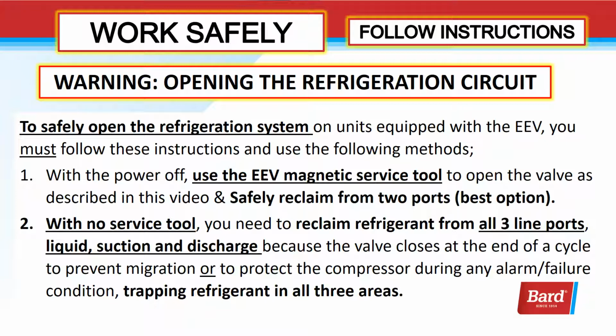With the power off, you can use the electronic expansion valve magnetic service tool to open the valve as described in this video and safely reclaim refrigerant from the two ports located near the compressor. With no service tool, you need to reclaim refrigerant from all three line ports, and that would be the liquid line, suction line, and discharge line. Because the valve closes at the end of a cycle to prevent migration or to protect the compressor during any alarm or failure condition, this will be trapping refrigerant in all three areas.